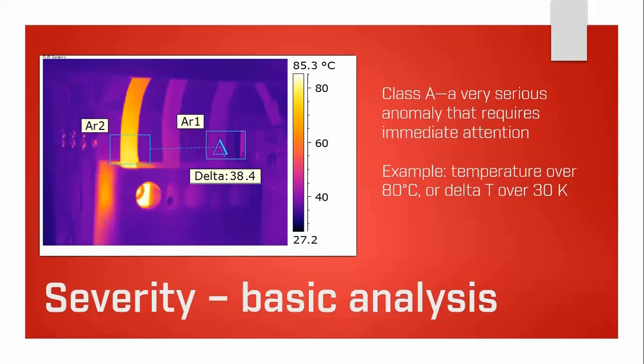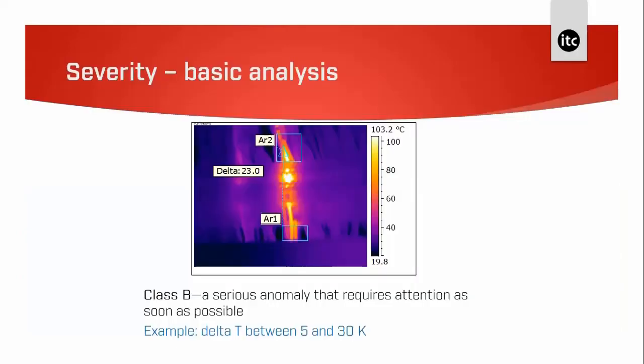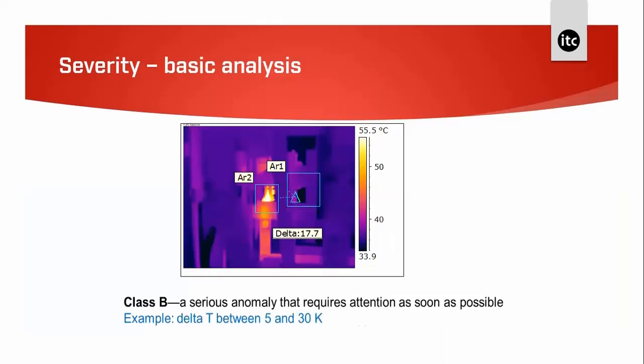Here's an example using full classification on a three-phase supply. The delta T is 38.4°C — a Class A problem straight away. You can see the importance of having good understanding of thermography and being able to measure delta T correctly. If you miscalculate the delta T, you could misclassify the severity. This next example shows a delta T of 23°C — based on our classification criteria, this is a Class B problem. This works on HV as well as LV.